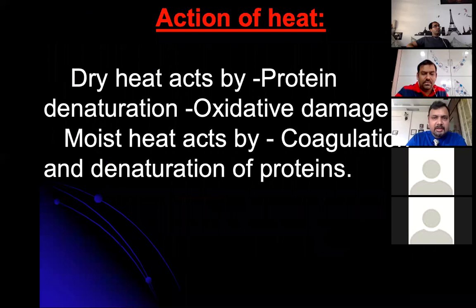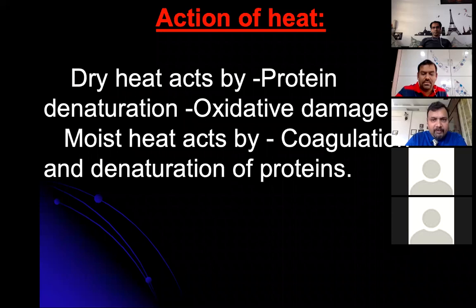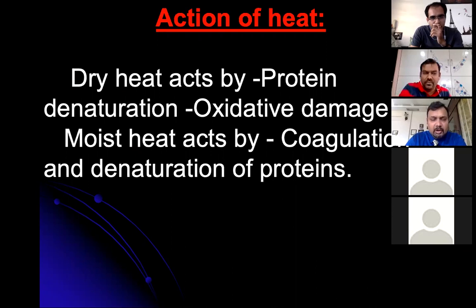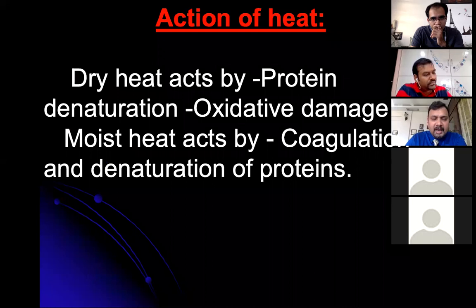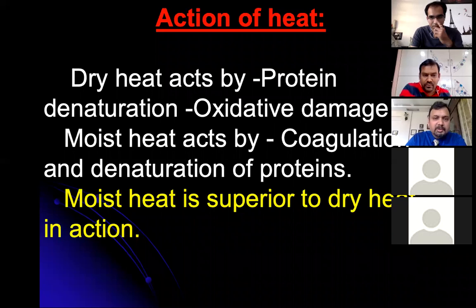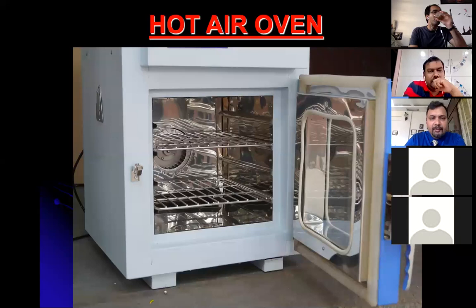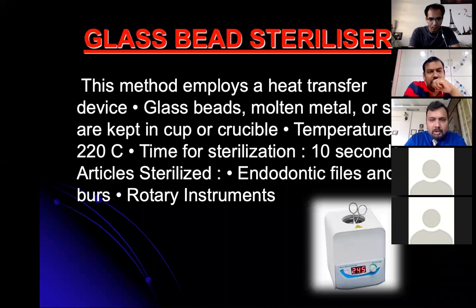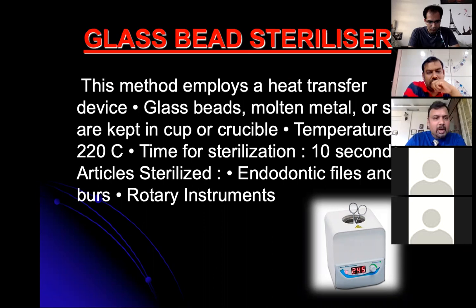Heat denatures proteins in the cell wall of microbes, breaking down the wall so DNA leaks out, killing the microbes. Moist heat coagulates proteins and does not allow further microbial growth, making it superior to dry heat. For dry heat, hot air ovens are used but less common now. The glass bead sterilizer operates at 220°C and sterilizes endodontic files, burs, and rotary instruments within 10 to 15 seconds.